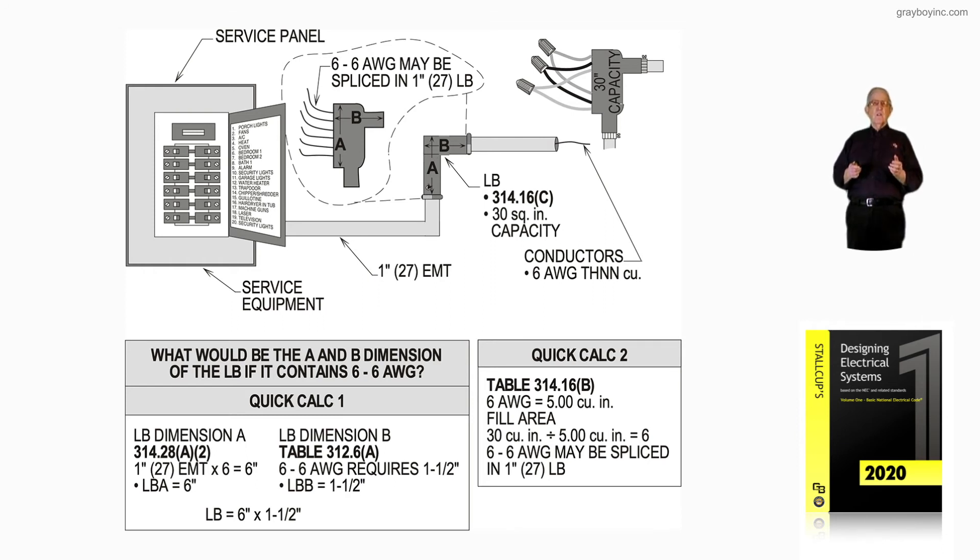Now, you notice in the illustration, you have six number six AWGs may be spliced in a one inch LB and then you have your A and B dimensions that it's calling for in quick calc one. Quick calc two is just showing that the conductors could be spliced there as long as the LB is listed as okay to do that.